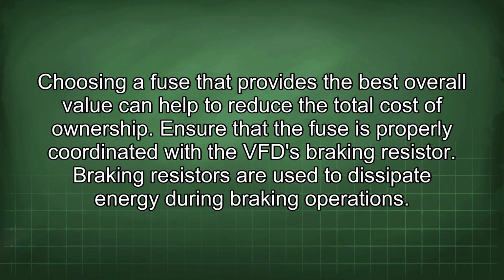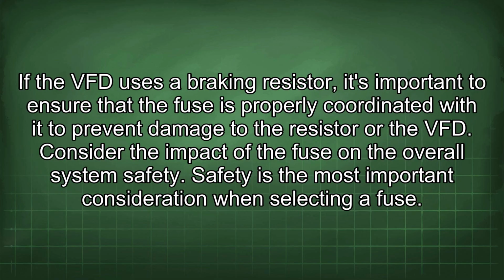Ensure that the fuse is properly coordinated with the VFD braking resistor. Braking resistors are used to dissipate energy during braking operations. If the VFD uses a braking resistor, it's important to ensure that the fuse is properly coordinated with it to prevent damage to the resistor or the VFD.